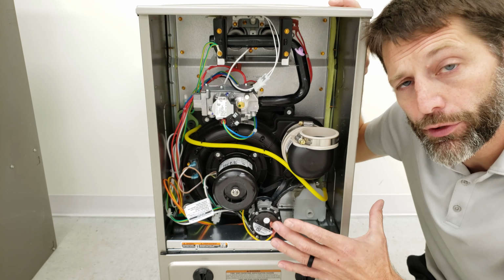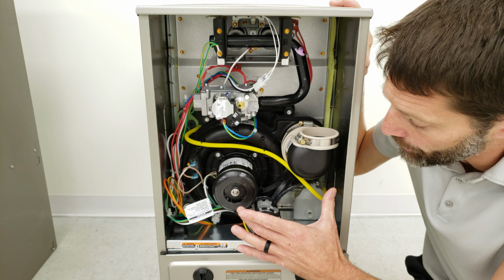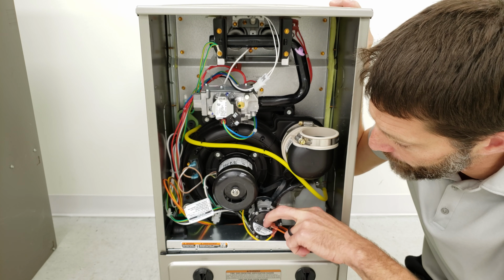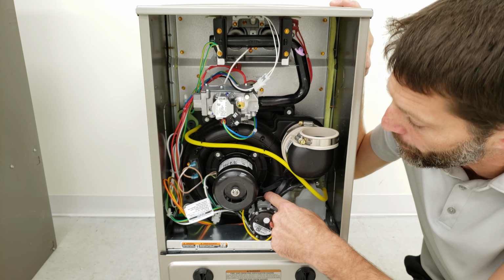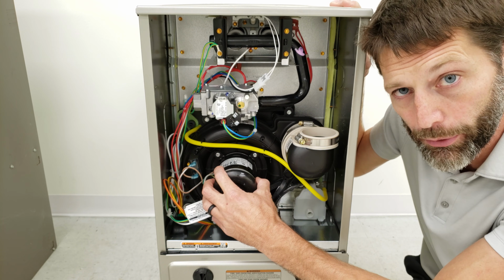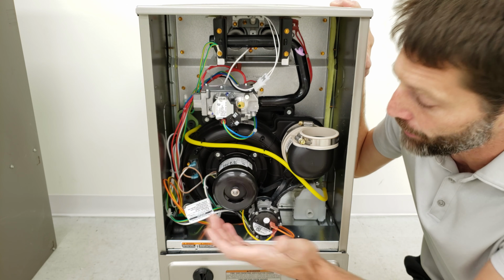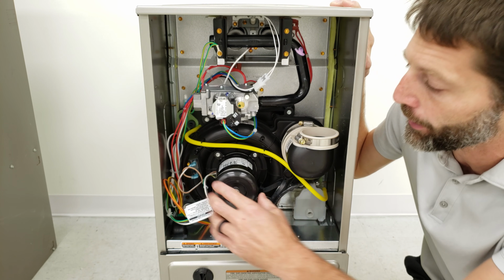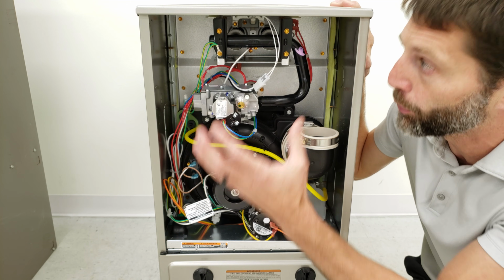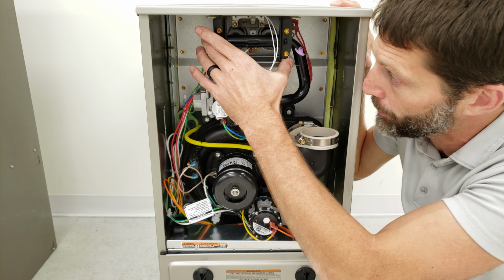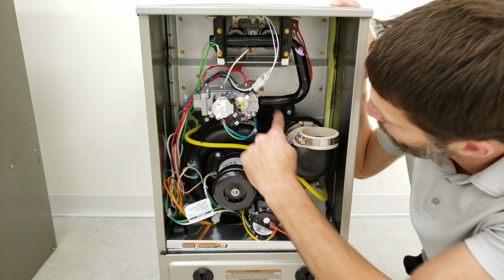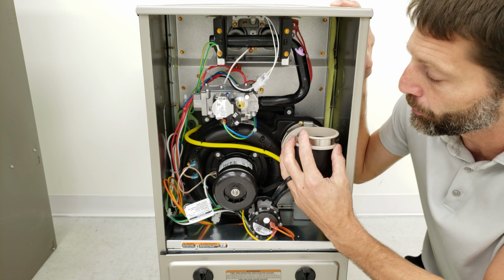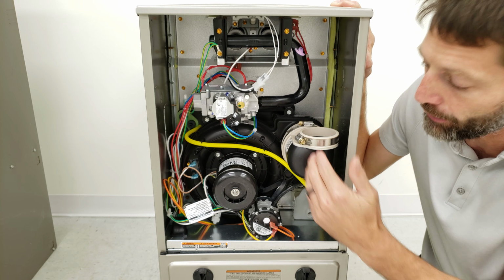This is a new high-efficiency gas furnace that hasn't been installed yet, and you see we have two pressure switches down here. The job of this pressure switch is to monitor the pressure on this inducer motor. If the inducer motor is not running, then the switch won't close. The inducer motor's job is to pull combustion air into this combustion chamber and then to pull the exhaust through the heat exchanger in the back and out through this exhaust pipe. It's going to push that exhaust out.